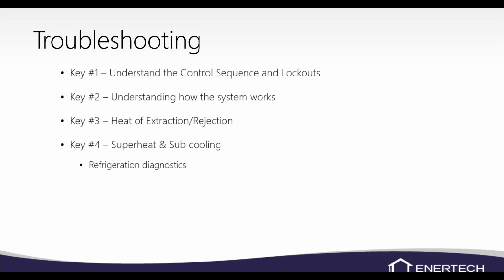Obviously, you have to understand superheat and subcooling. If your heat of extraction and rejection don't work out, then we would go put the refrigerant gauges on there, check our superheat and our subcooling, and do some refrigerant diagnostics. We've got to know where to start looking when we get a fault, or the unit's not operating properly, or our superheats or subcoolings are off. If there is a lockout, the lockout board will tell you high pressure, low pressure, flow, that kind of thing. So it'll give you an idea of where to start looking. So we'll go ahead and dive in here.